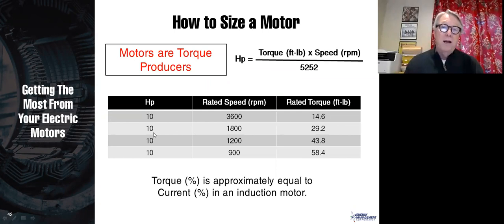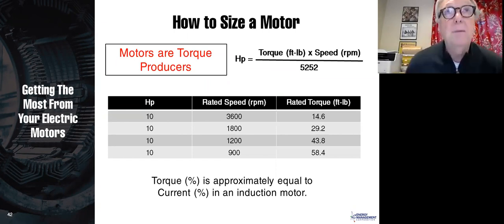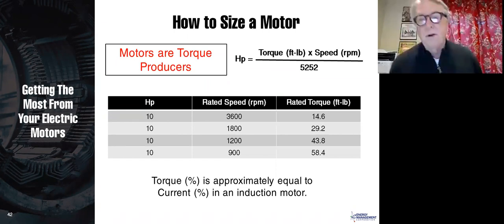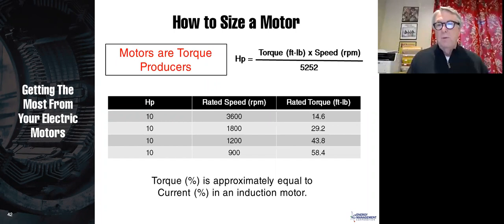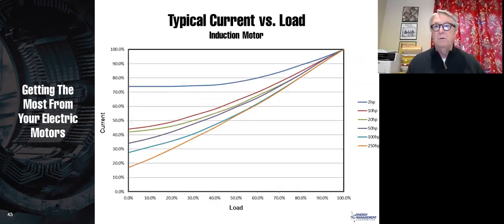And you will find, let's say you go out and you look at a price on a 10 horsepower 1800 RPM motor. Then you look at a price on a 10 horsepower, 900 RPM motor. They're both 10 horsepower. They ought to be the same price, but they're not. The 900 RPM motor will probably be double or maybe even more than double the price of the 1800 RPM motor because it's producing more torque. And the torque is proportional to the fluxes inside that motor.